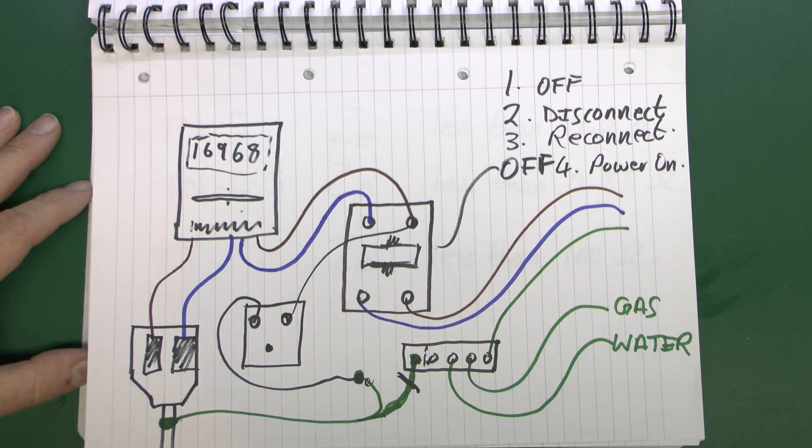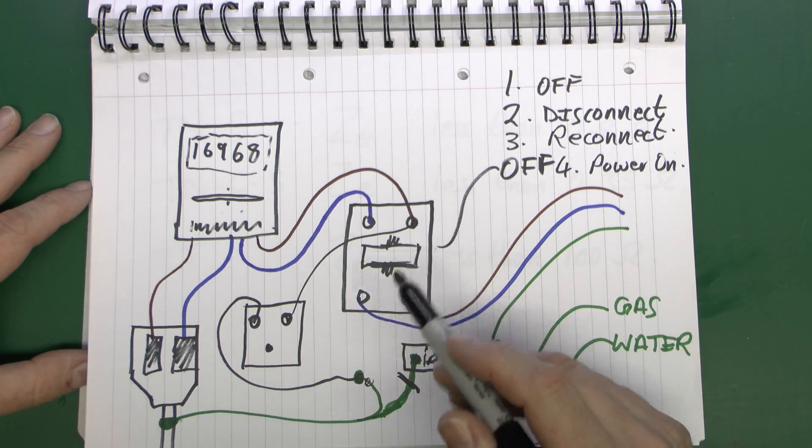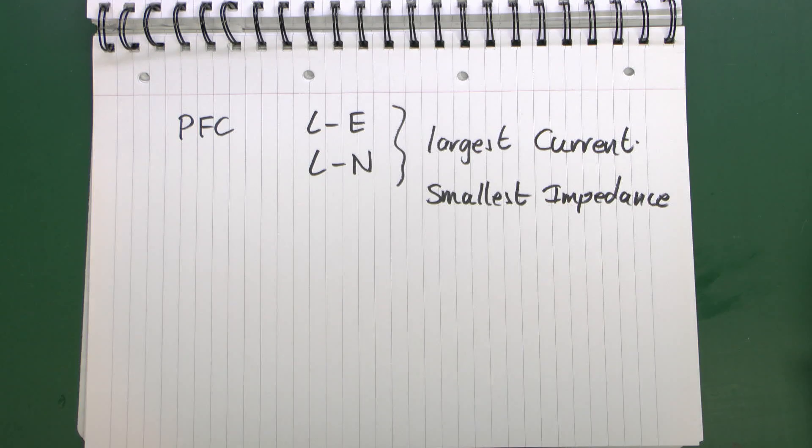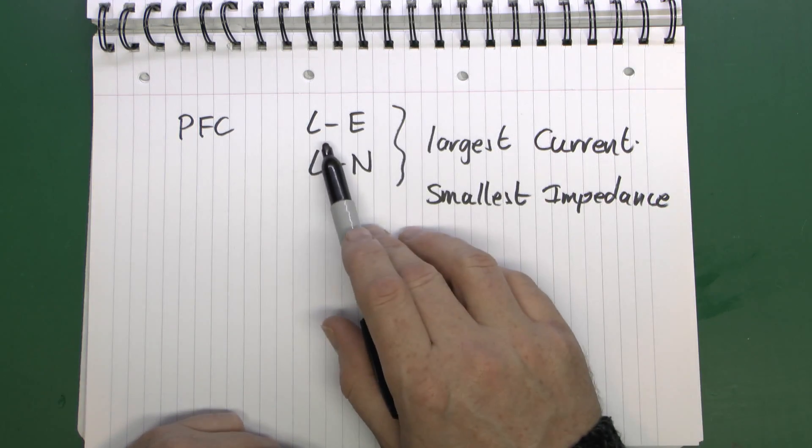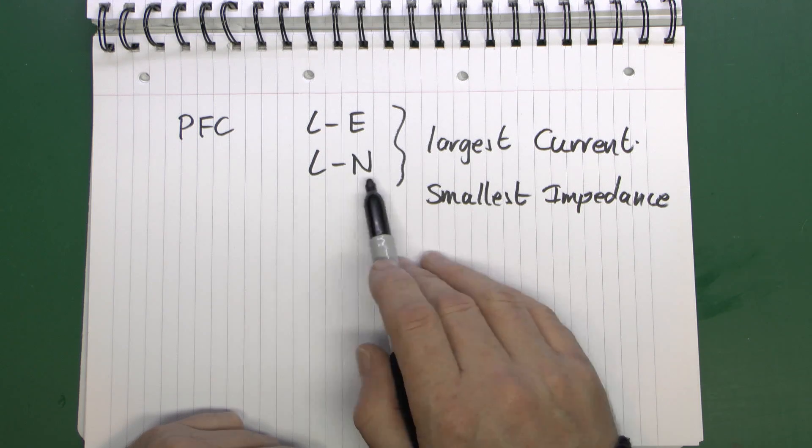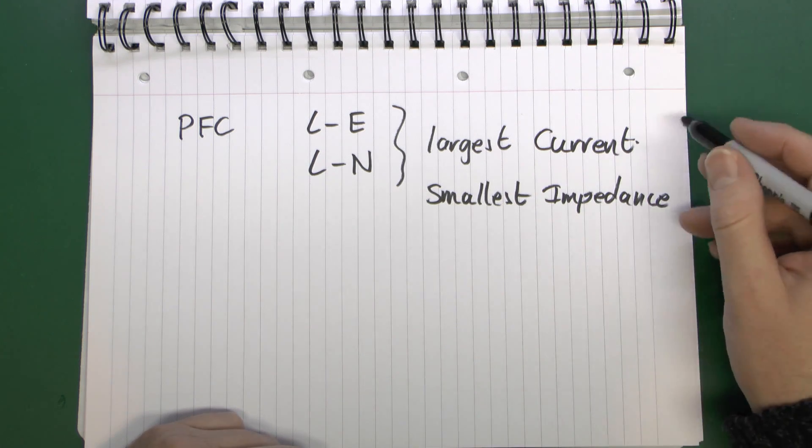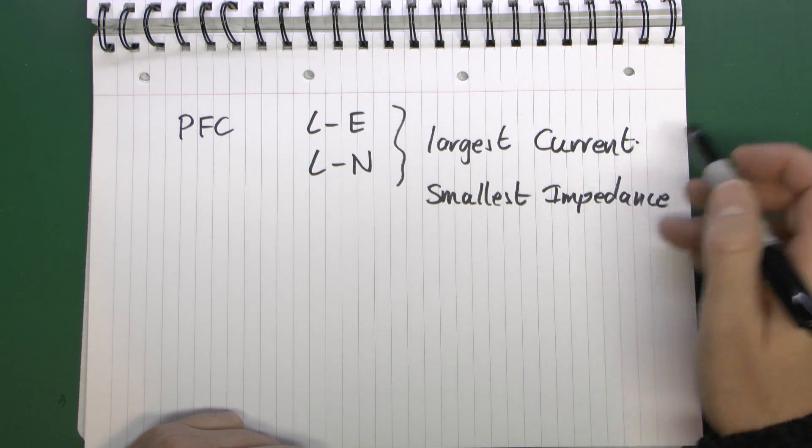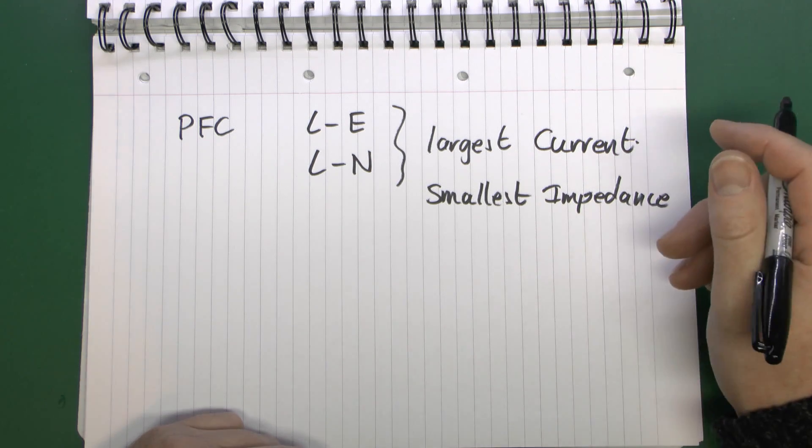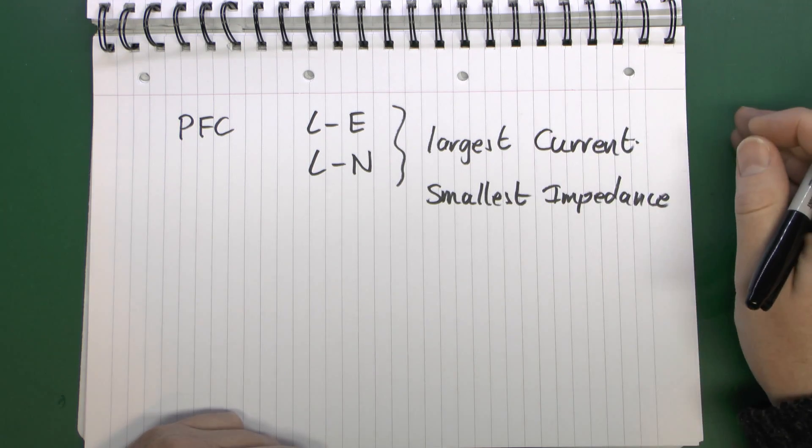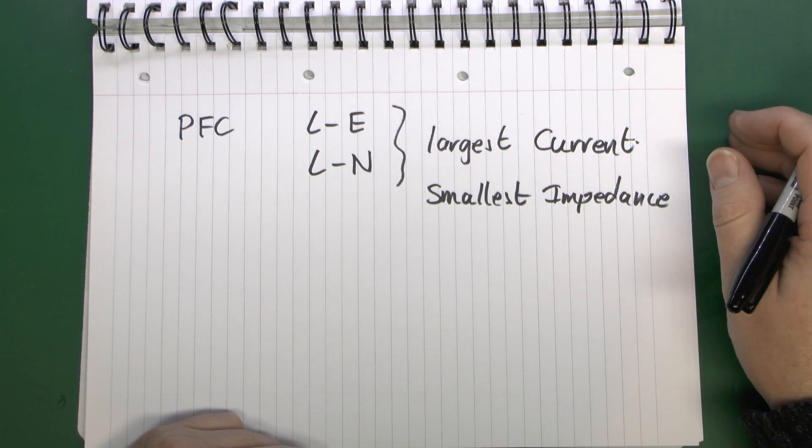So as well as testing there, you do need to once you've done this, test between the line and neutral, and whichever value is highest for the fault current is the one that you would record. So in terms of the prospective fault current, you would test between the line and earth, and then also between the line and neutral, and whichever came up to be the largest current, and of course that would also mean the smallest impedance, would be the value you would record for the prospective fault current. And say on the TNCS system you would expect those to be exactly the same because you're testing the same cable, but on other systems there will be considerable variance in that.